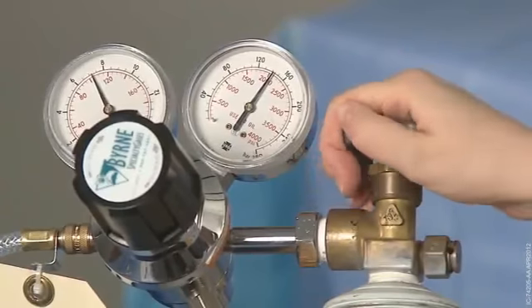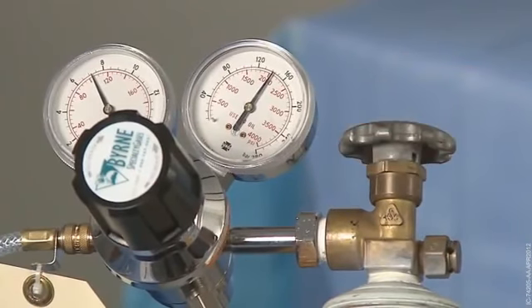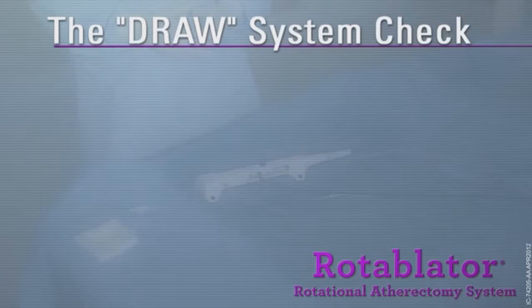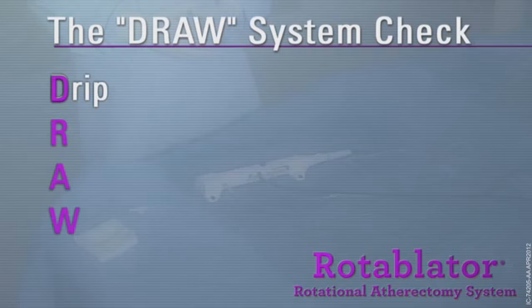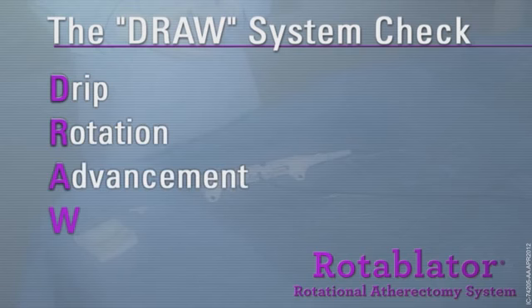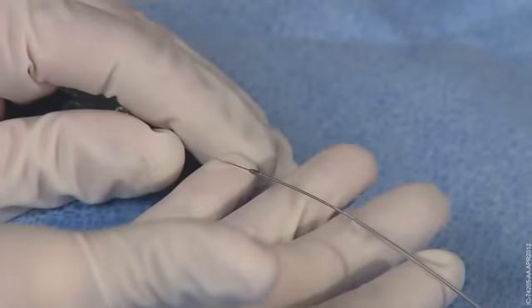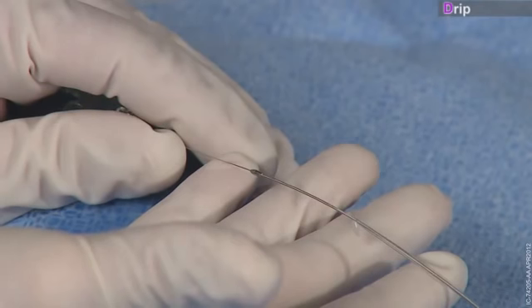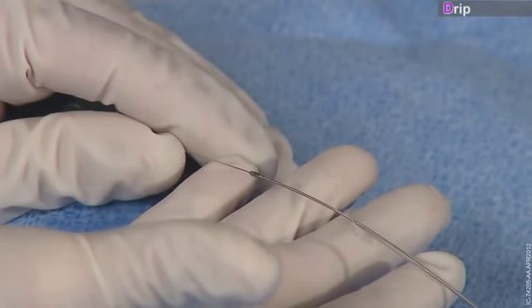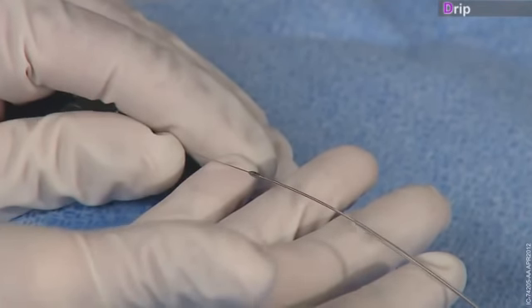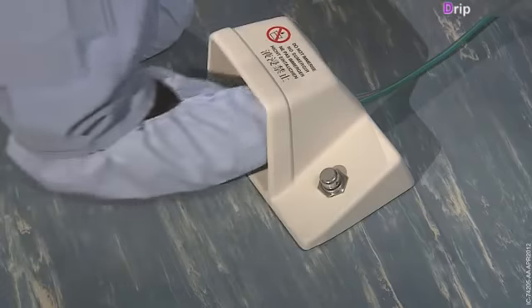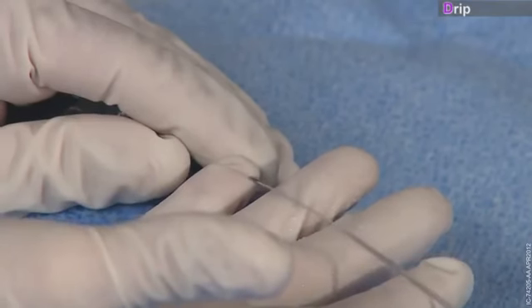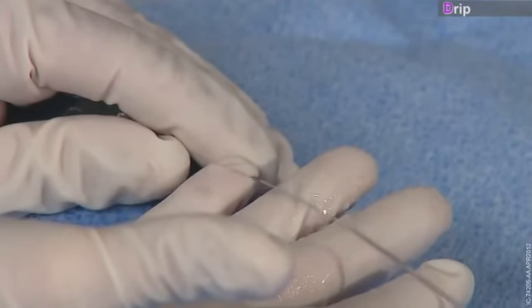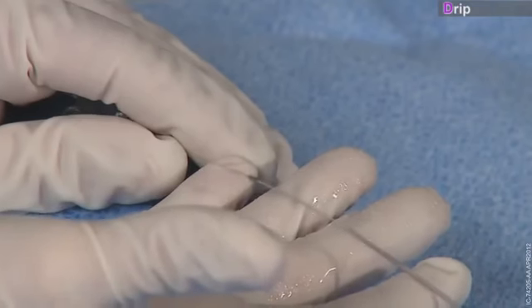Check the valve on the air tank to ensure the system is pressurized. The acronym DRAW will help you remember these steps to checking the system. This stands for drip, rotation, advancement, and wire. First, verify that there is irrigation at the distal tip of the burr catheter. The drip rate should increase when the system is activated with the foot pedal. Once activated, make sure the burr is not in contact with the table drape.